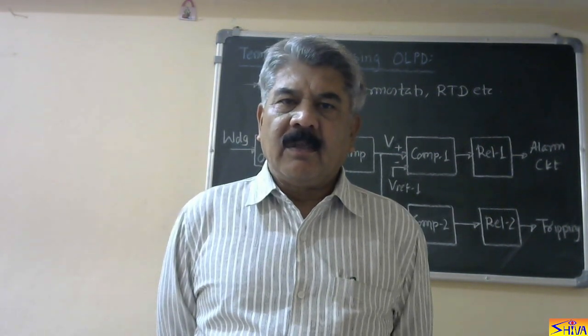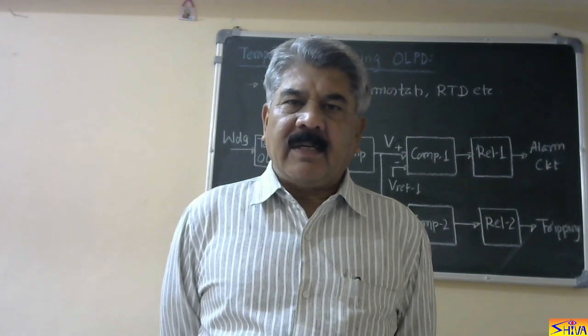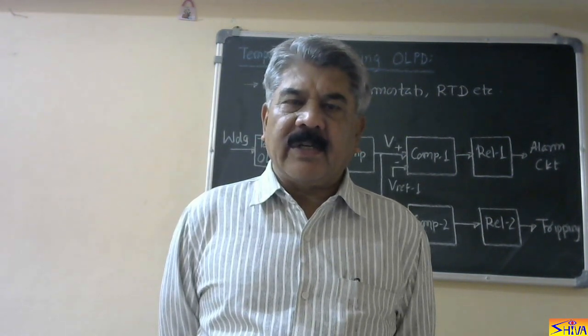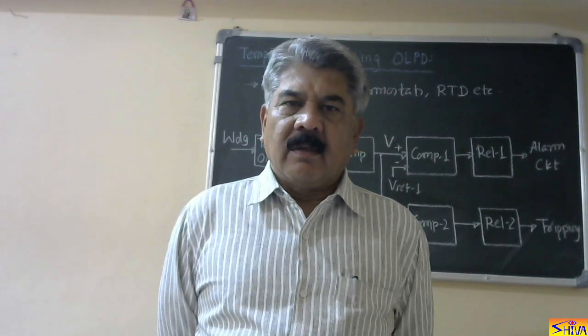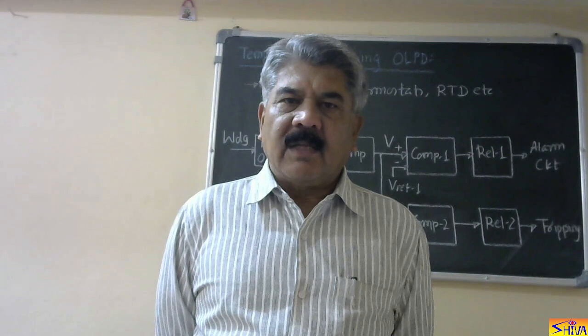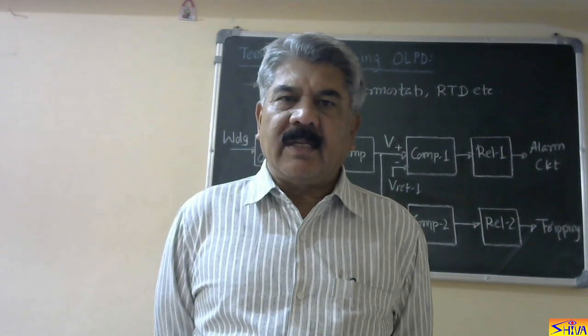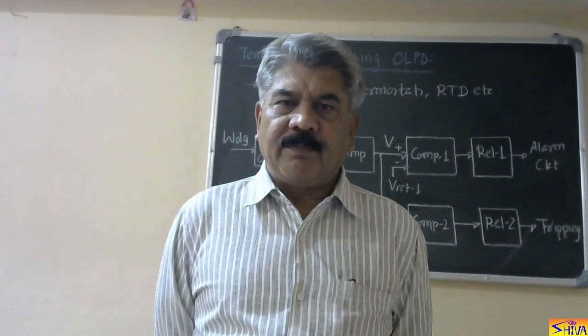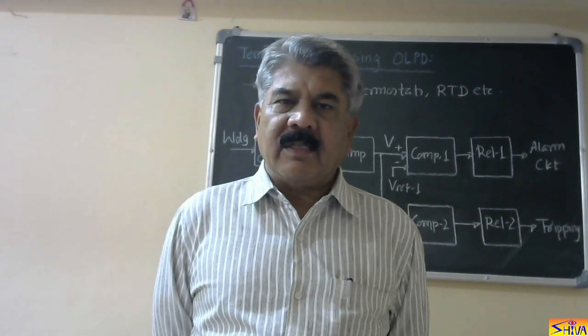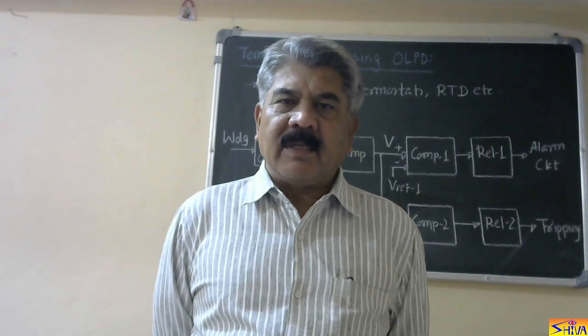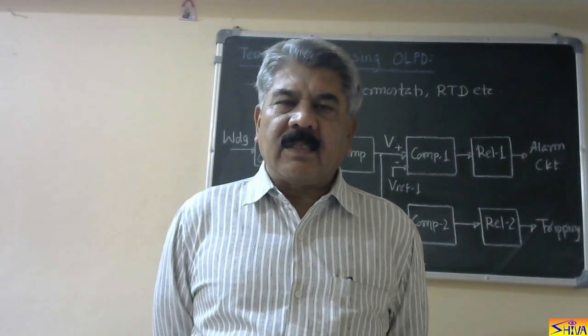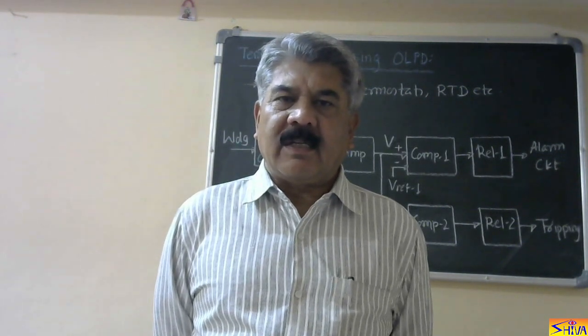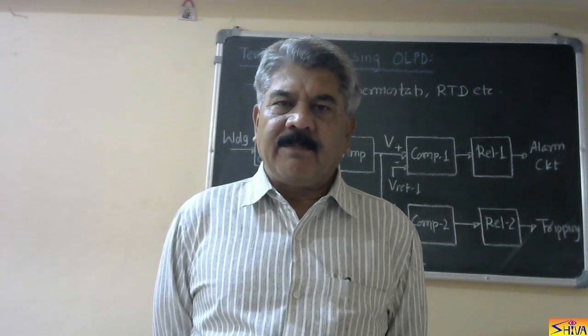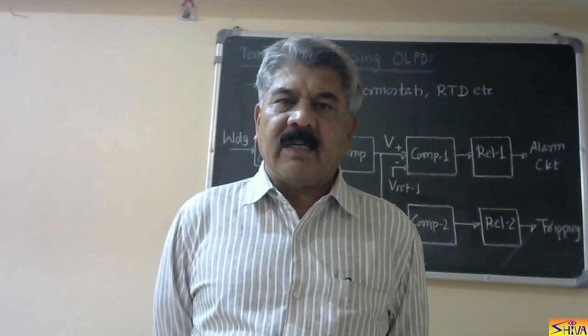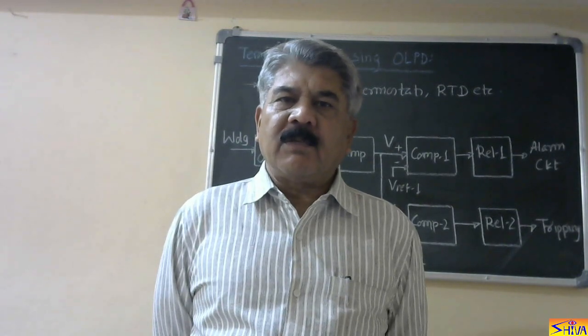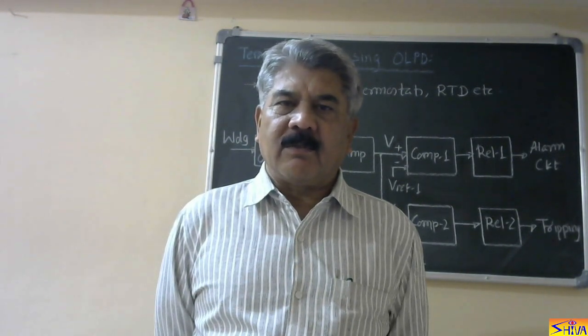One is current sensing. Now this current sensing protective device can take care of overload condition, under voltage condition, single phasing, stalling, as well as current increase due to any reason, and it can be due to heavy starting also. Now when we come to the temperature sensing protective devices, they can take care of high ambient temperature, failure of cooling system, because when cooling system fails, temperature increases, but this does not increase the current. Therefore current sensing protective device cannot detect the failure of cooling system. Now cooling system is provided for large induction motors and very large induction motors.